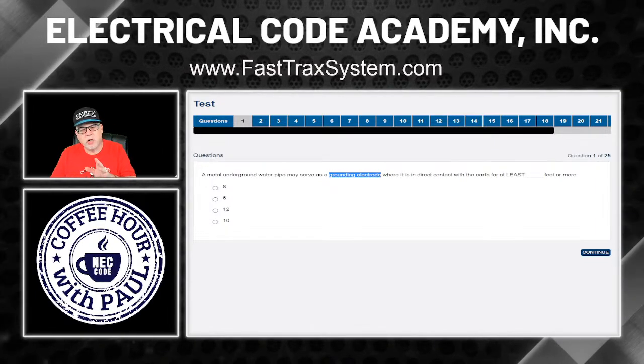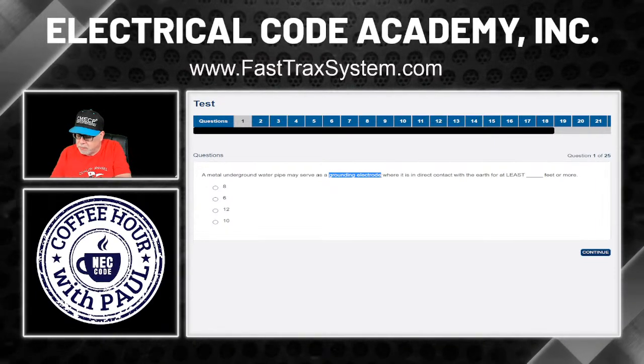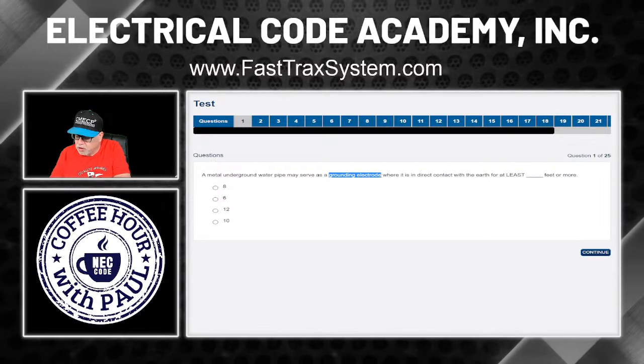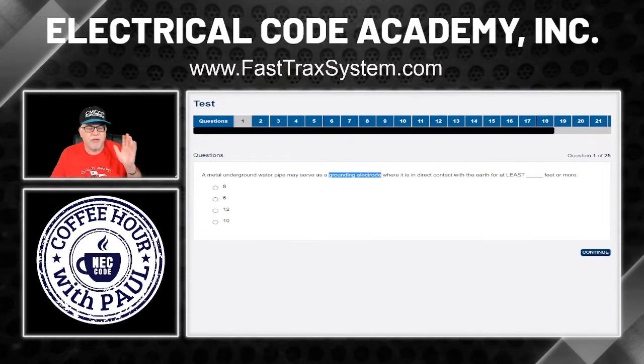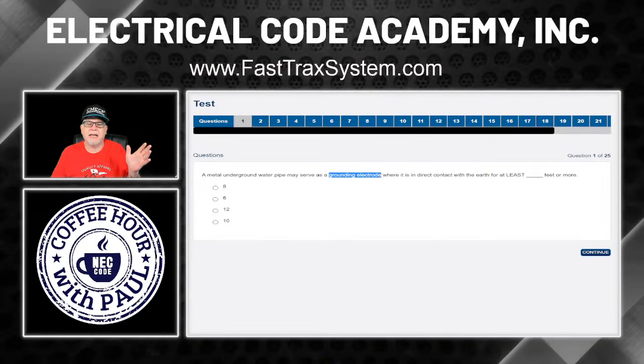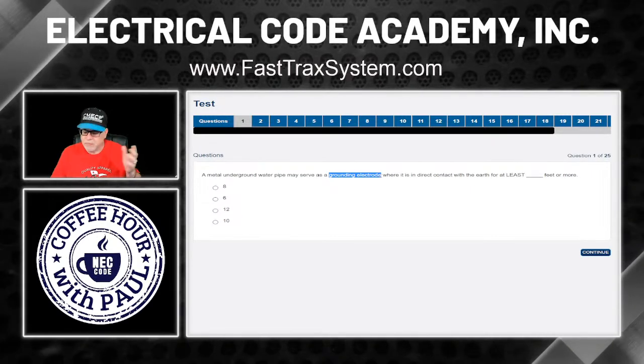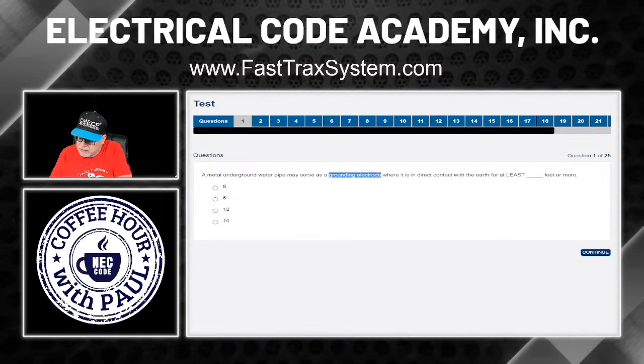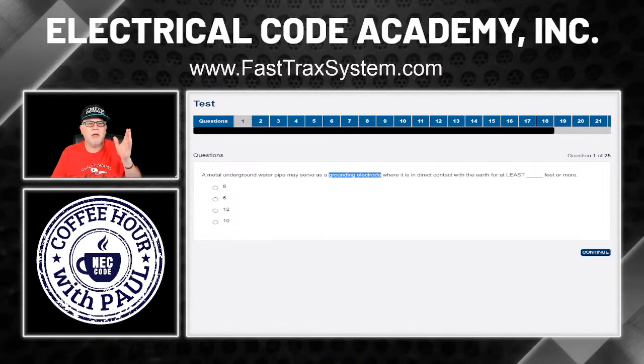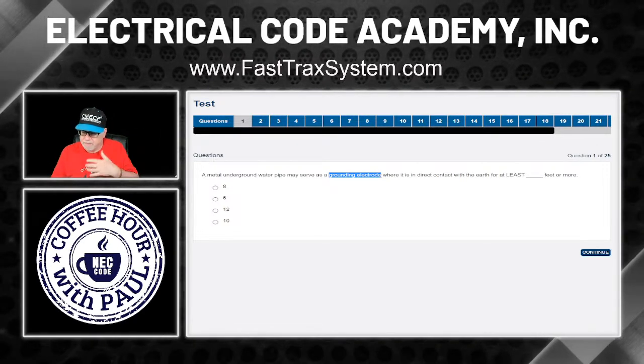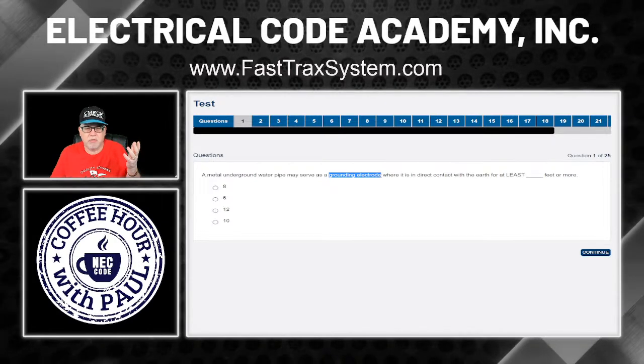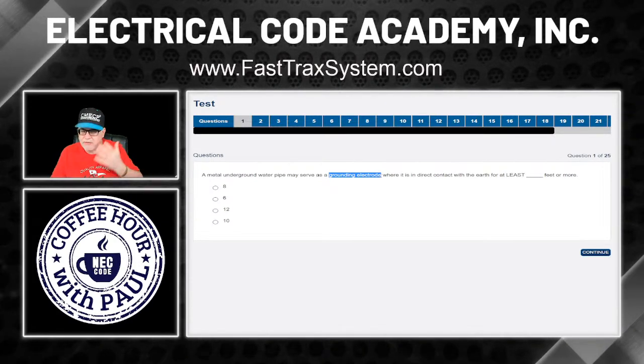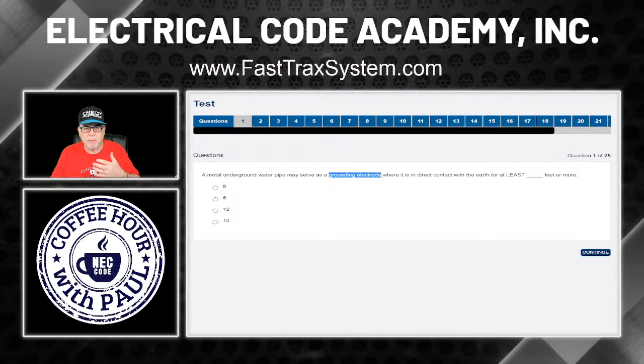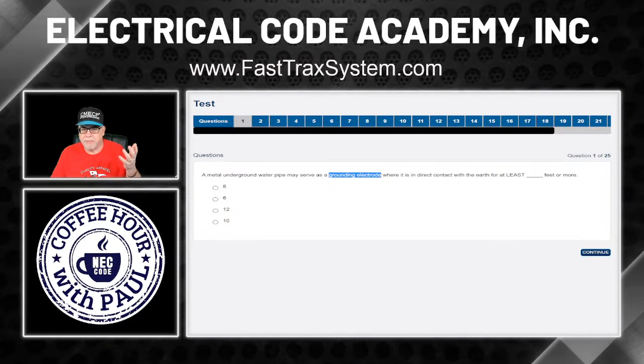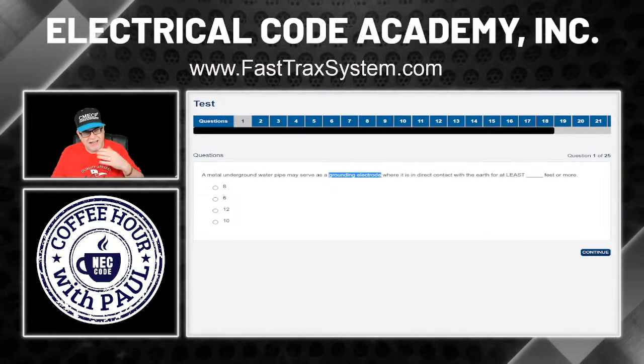Because what you're going to do is dissect this. Here it says metal water pipe. So you would have gone to 250.30 and looked at it, and you would have said, well, okay, I get it. That's separately derived system. Then you would have gone to 250.52, and you would have gone, hey, that's grounding electrode types, a different list of ones. And A1 happens to be the water pipe type grounding electrode. So that's how you would do it.